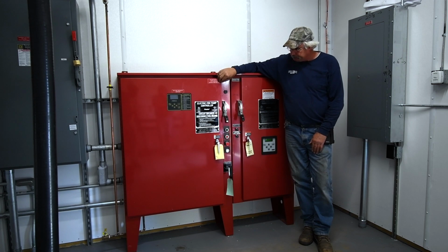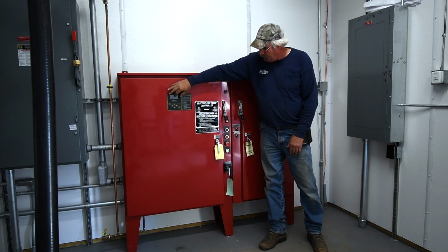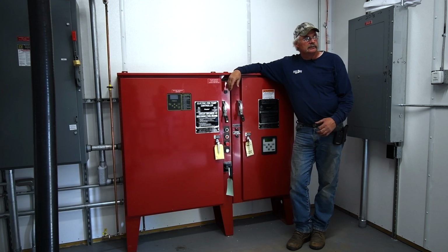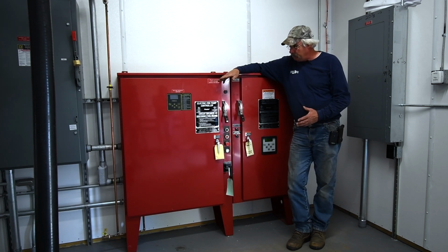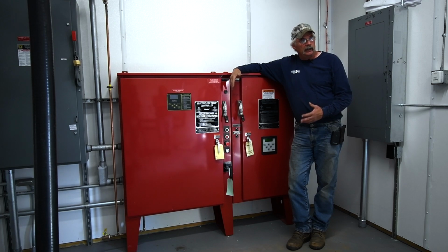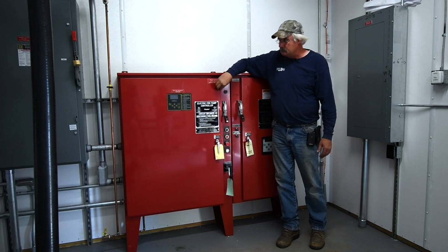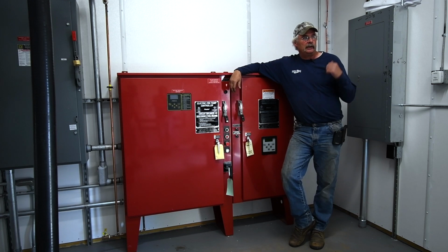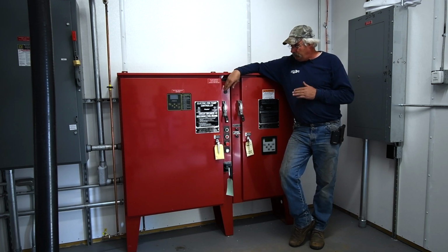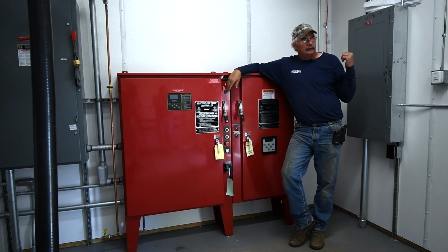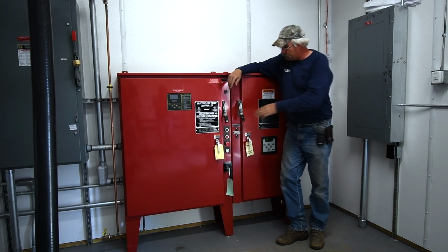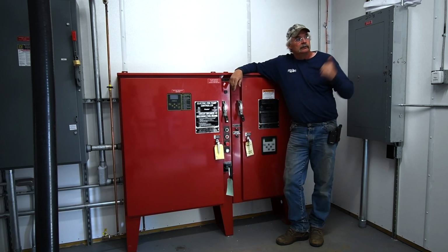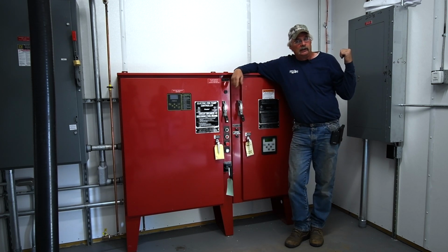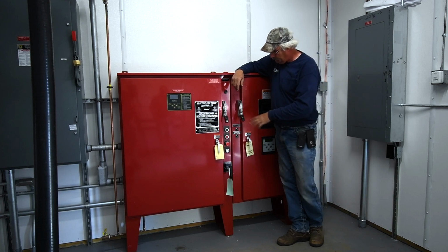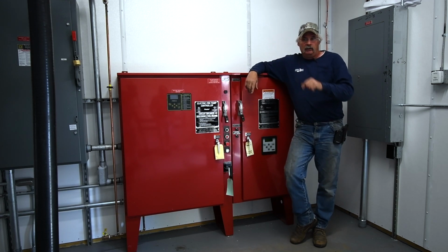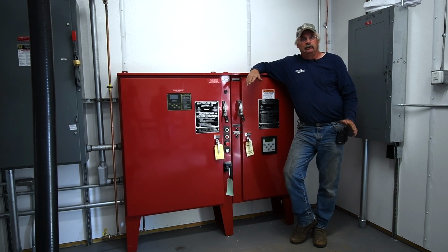This cabinet has a visual sight glass. It tells you your pressure, your RPMs, what the pump is doing. It tells you phase reversal. It tells you your amperage, your voltage. This cabinet's tied back to your panel. If the pump is running, the fire alarm panel will pick it up. If somebody shuts the power off feeding the controllers, the fire alarm panel will pick that up, power loss to your fire pump. If you have phase reversal, that pump will run in reverse. It just won't build any pressure.